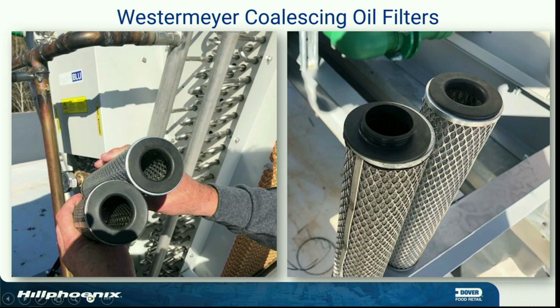And what we started seeing once we got above 93 degrees and 238 on the discharge line, we would get a lot of bypass, right? And everybody's seen it. You get those sensors that come on in the summer and they never shut off. Well, that's what happened. We were getting too much bypass air, and once that switch fired, there was enough heavy vapor-laden oil in there that it kept the switch fired. And it would not shut off until you got down to about 1100, 1050. Those were hot, solid numbers you could use every day. It was amazing. Yep. When it cooled back down, we'd go back to normal operation.